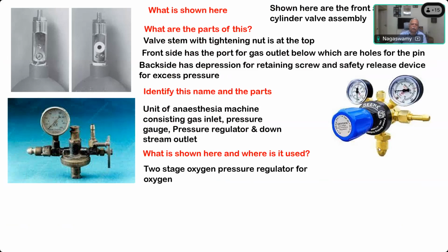Usually these were used in older days. Nowadays every part of the hospital, especially all the corporate hospitals or medical college hospitals, everywhere you see there is a central pipeline outlet for oxygen, suction, air, everything. But in older days they never used to have pipeline for the ward, or even the ICUs did not have pipeline supply. So they used to use the large cylinders with this pressure regulator attached to that. So if you want to use it for a ventilator, you can reduce the pressure to 40 to 50 psi. And in case you want to use it directly for an oxygen mask or cannula, you can reduce it to 15 to 20 psi.